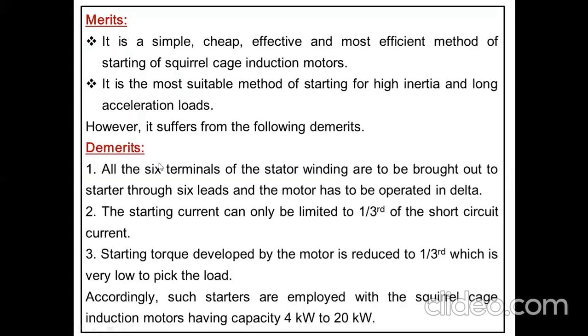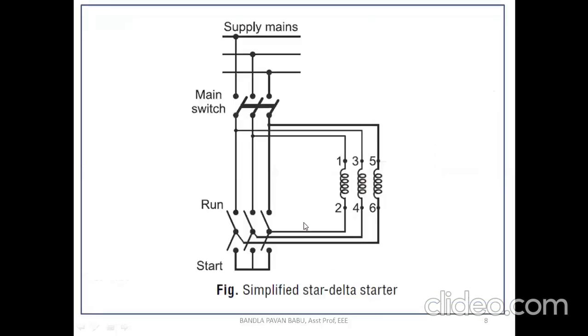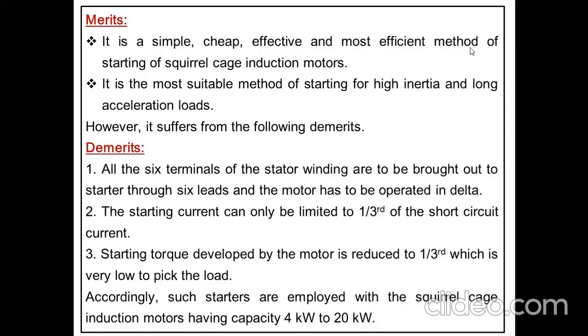And there are some demerits. Let us see. All the 6 terminals of the stator winding are brought out to the starter through 6 leads, and the motor has to be operated in delta. All the 6 terminals, we can see here: 1, 2... so 6 terminals are there, that is 1, 3, 5, and 4, 6, 2. So that is the case.